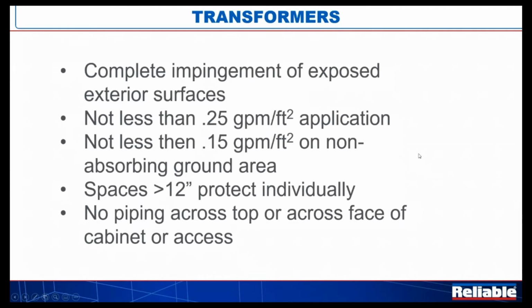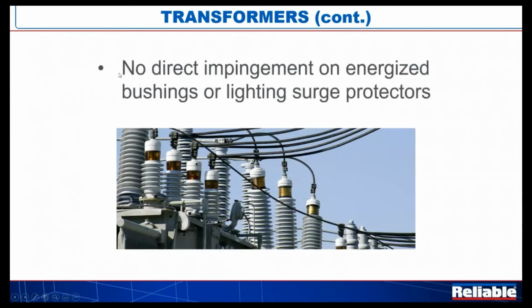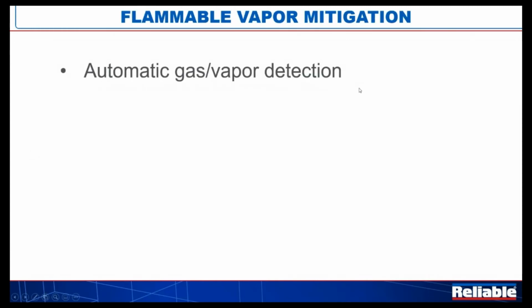And then finally, we do say complete impingement of all exposed exterior surfaces. Well, that's except the energized bushings or the lightning surge protectors. Those ribbed things that you see sticking up when you drive past the substation, those are what they call the bushings. Even though they're sitting out in the rain, when we discharge our fire protection onto it, typically the transformer would hopefully be shut down, but we don't want to create a case where there's so much water that we're direct shorting between these energized areas of the transformer.